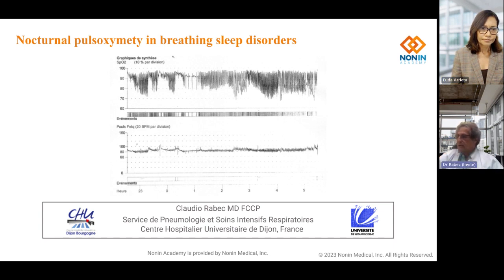In fact, the threshold is important because the threshold of the pulse oximeter is dependent on two different things. The first one is the level of oxygen saturation, the level of baseline oxygen saturation. And the second one is the aspect of the oxygen curve. The first one will give you the state of oxygenation, and the second one will give us the events that could compromise the oxygenation of the blood. In the first one, we will evaluate the level of oxygen in the blood, and in the second one, we will evaluate the presence of some events that can compromise regularly and periodically the level of oxygenation, for example, in the case of an apnea or hypopnea.